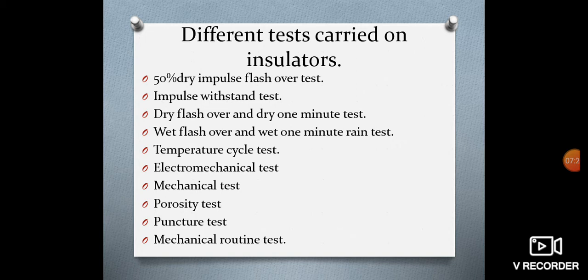Wet flashover and wet 1 minute rain test. This test is carried out under artificial rain. It is called wet flashover test. The insulator is subjected to spray of water of following characteristics. Precipitation rate 3 plus or minus 10% millimeters per minute. Direction 45 degrees to the vertical. Conductivity of water 100 microsiemens plus or minus 10%. Temperature of water at ambient conditions should be plus 15 degrees centigrade.